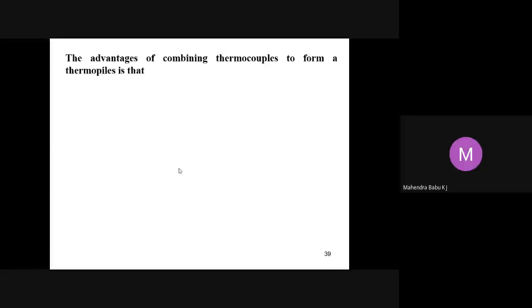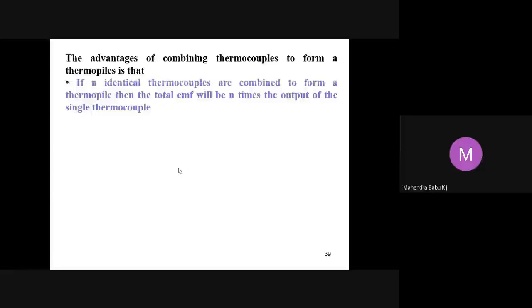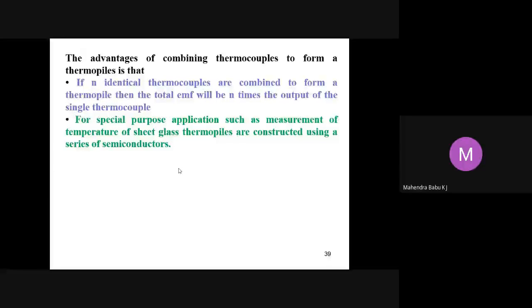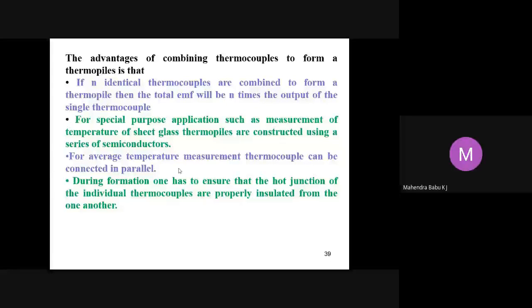The advantage of combining thermocouples to form a thermopile is that, suppose n identical thermocouples are combined to form a thermopile, then the total EMF will be n times the output of the single thermocouple. For a special purpose application such as measurement of temperature of sheet glass, thermopiles are constructed using a series of semiconductors. For average temperature measurement, thermocouples can be connected, instead of series, in parallel. During formation, one has to ensure that the hot junctions of the individual thermocouples are properly insulated from one another.